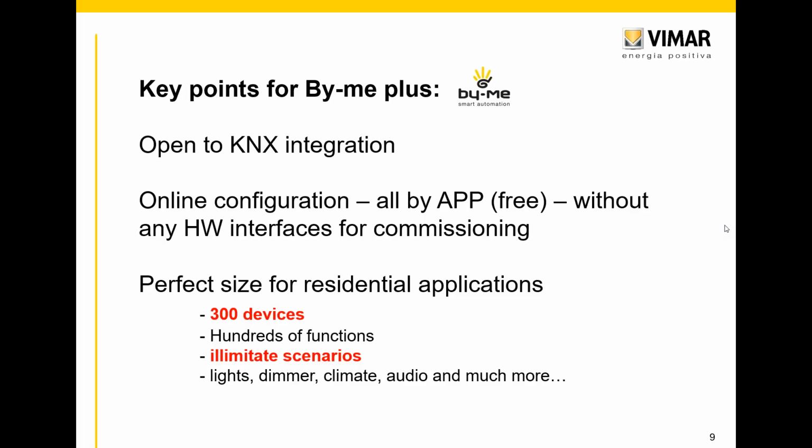transparent to KNX to achieve the full integration with the KNX system. Obviously, we are talking about a different system, so I cannot configure By-me through the KNX tools and vice versa, but they are able to talk to each other without any hardware interface in between. We improve the configuration and commissioning with the online configuration with an app.